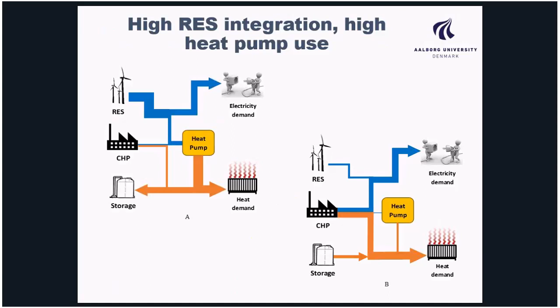In future district heating systems, large-scale heat pumps are expected to function well in fourth generation district heating systems. That is because there will be more accent put on power-to-heat solutions, but also because the temperatures in such a district heating system will be lower, approximately 50 to 60 degrees Celsius, which makes a better case for larger scale heat pumps as they can achieve higher efficiency.